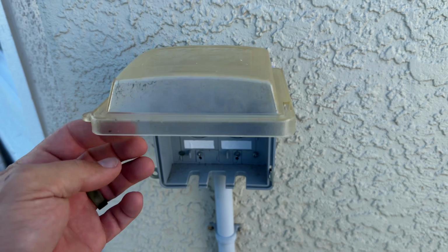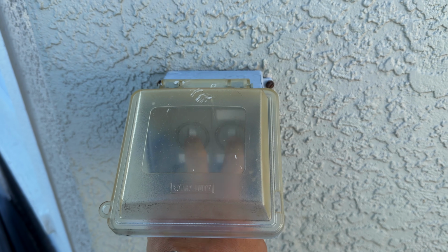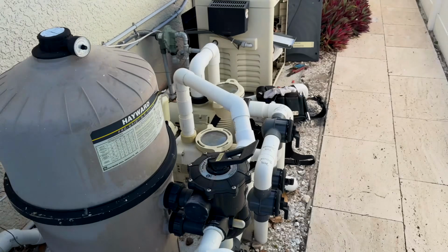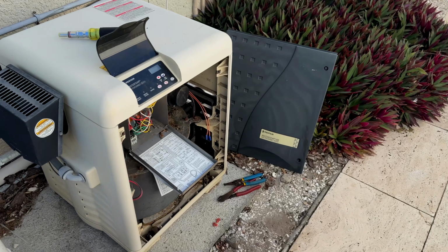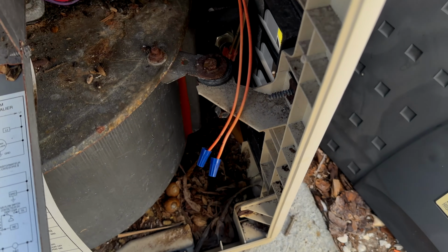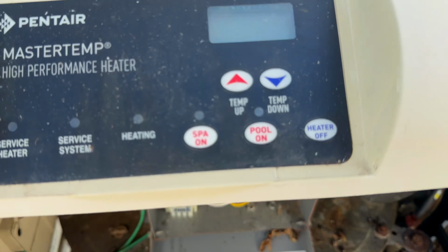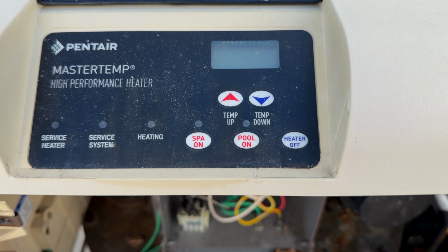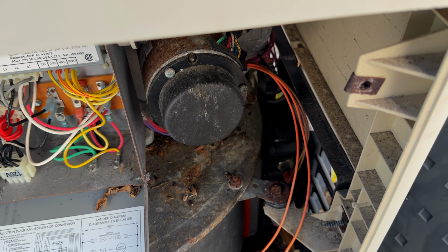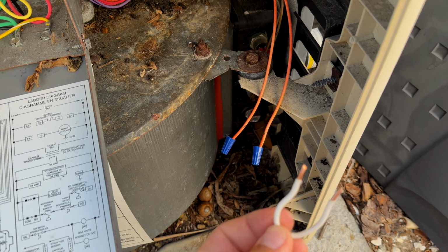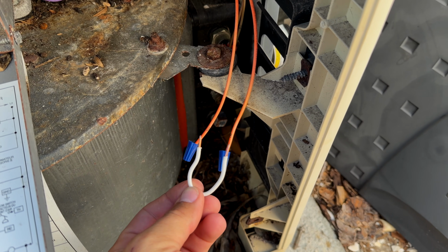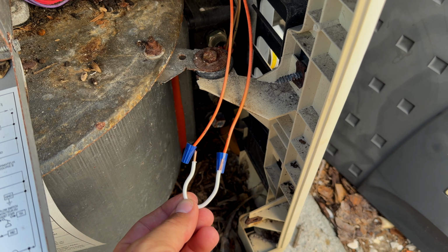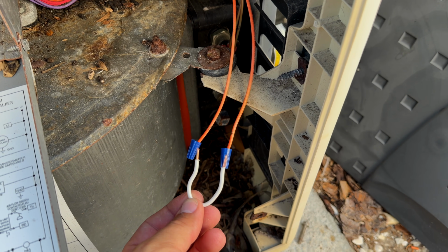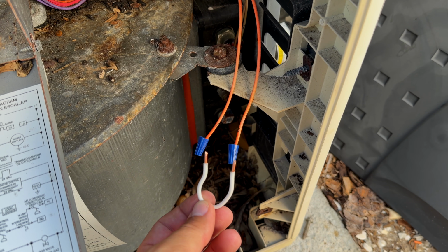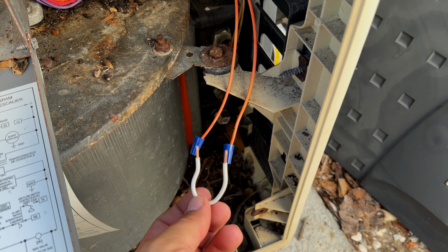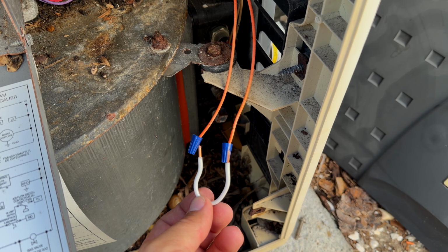It's real important to turn the heater off when you're working with voltage. Even though this is post transformer, you don't want those wires touching together that I had wing-nutted separately, because if they touch, you'll probably blow the fuse. So now we've got the power off to the heater. What we're going to do is effectively install a little jumper with some 12 gauge wiring and connect these two wires and see if the heater fires up from there. If it does fire up, it's just the high limit switch, and if not, we'll find another error code on the board underneath. So I'm going to do this off camera.